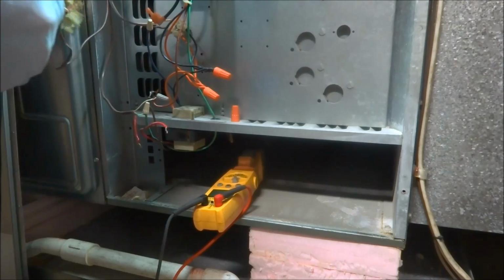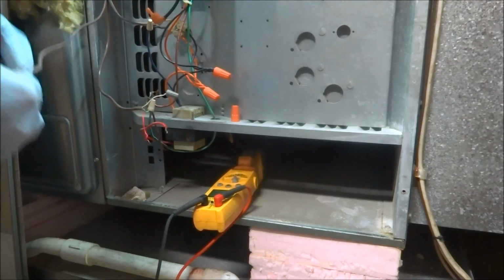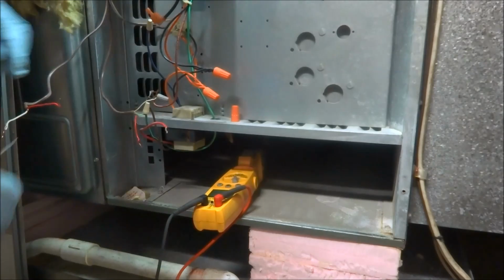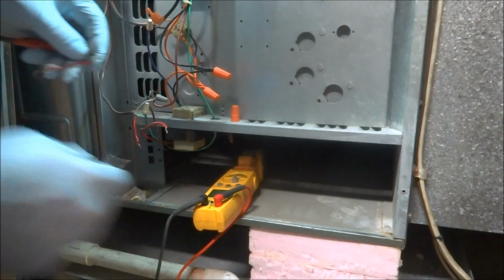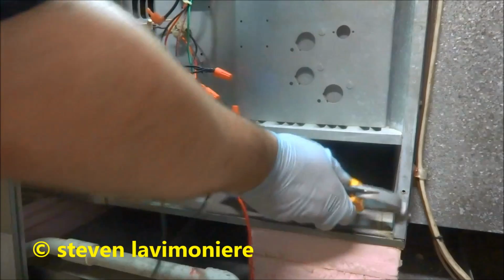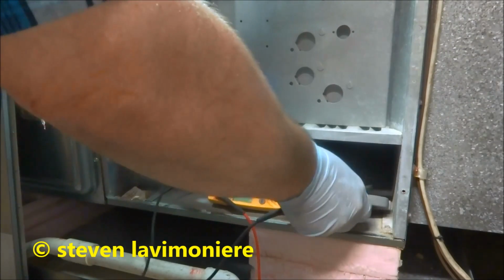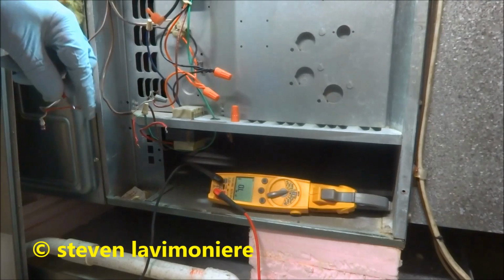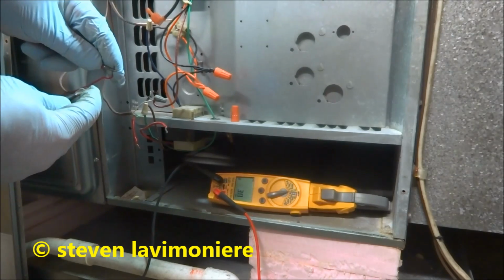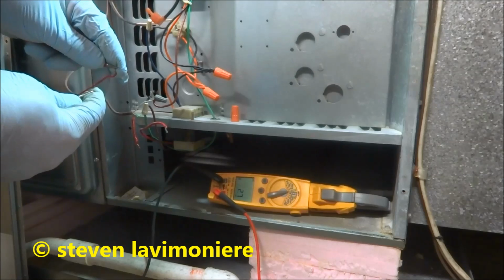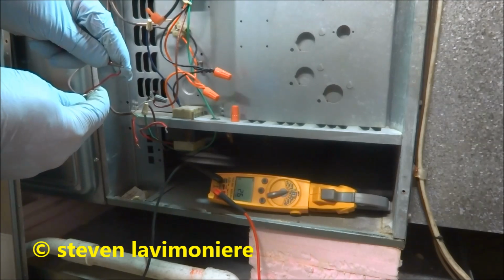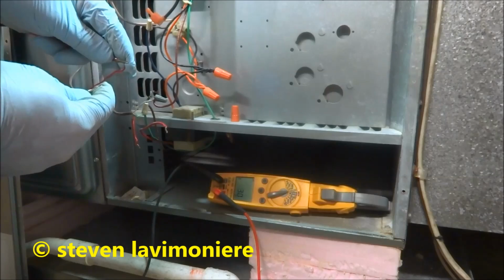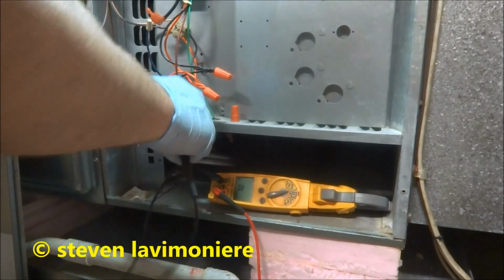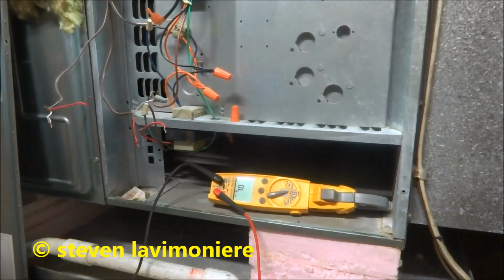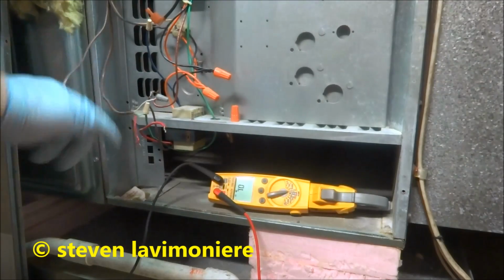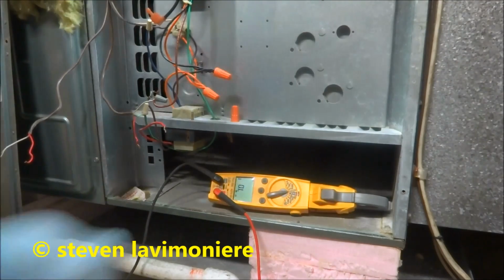Yeah, I must have a bad contactor. I'm like 2.8 on the ohms. So we got a bad contactor outside. That's what fried the transformer. I don't know if you guys can see that or not, but see the low ohms? 2.7. It's got a bad contactor outside. That's what fried the transformer, so I'll have to put a new transformer and a new contactor outside, and I should be okay. So the contactor shorted out, and then it shorted this out.